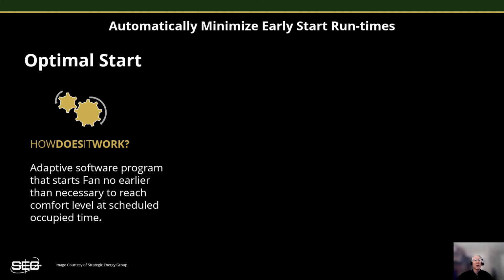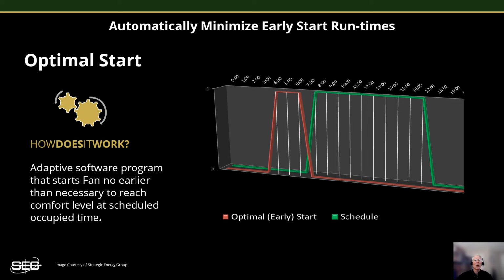This is an algorithm built into most modern automation systems that's designed to automatically adjust and minimize the daily early start period needed each morning. Colder mornings will require an earlier start, while milder mornings will require less. Some days may require no early start time at all. And by automatically readjusting this daily, it will provide much tighter early start control and can be a significant energy saver over the long term.